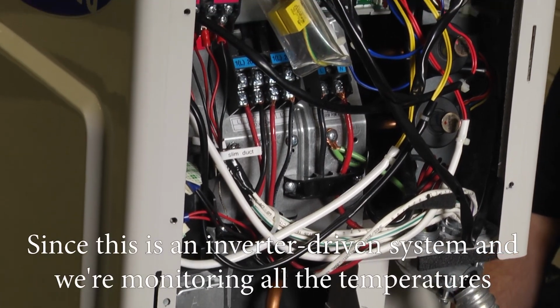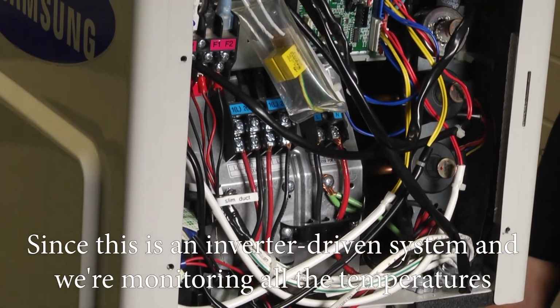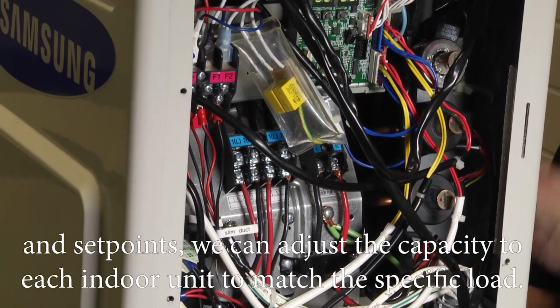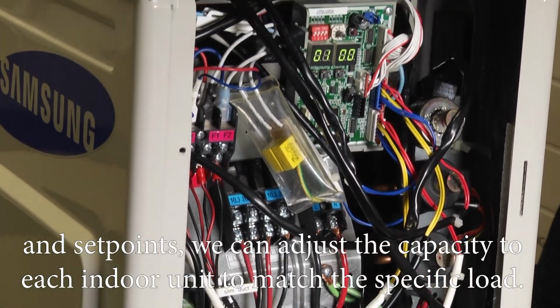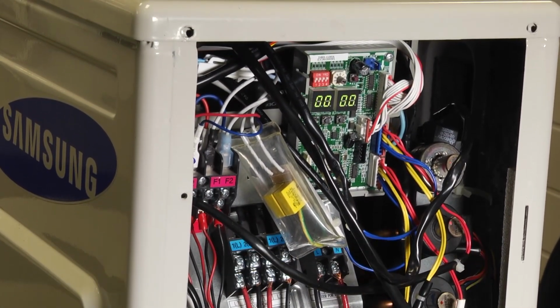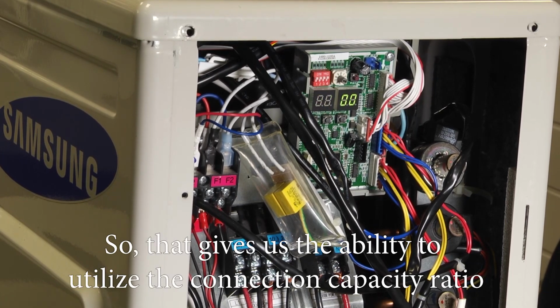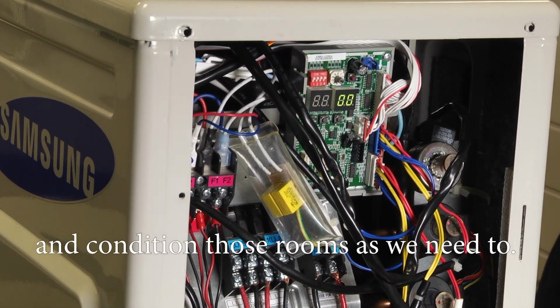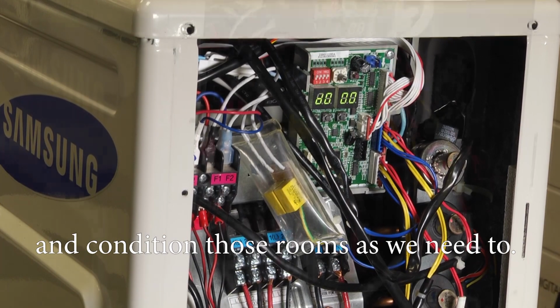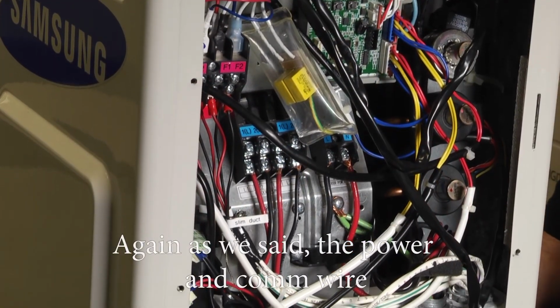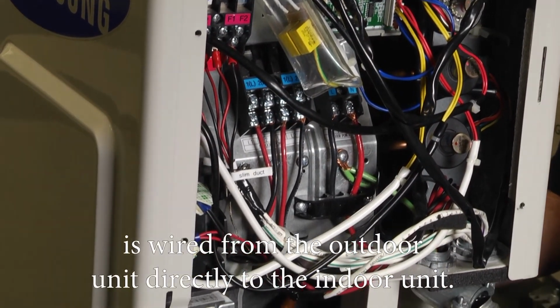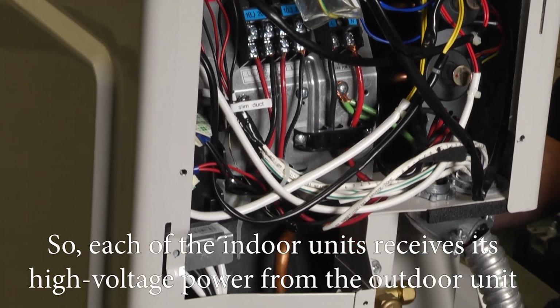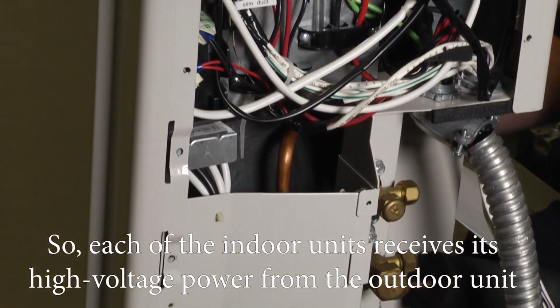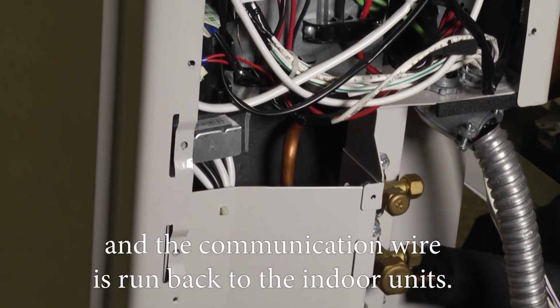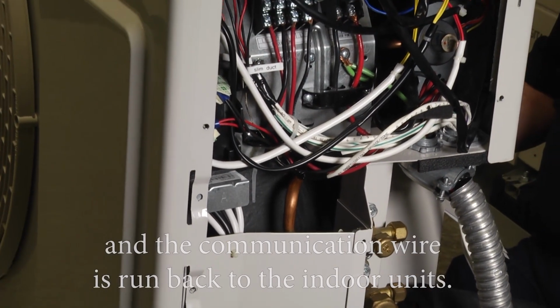Since this is an inverter-driven system and we're monitoring all the temperatures and set points, we can adjust the capacity to each indoor unit to match the specific load. So that gives us the ability to utilize connection capacity ratio and condition those rooms as we need to. Again, as we said, the power and comm wire is wired from the outdoor unit directly to the indoor unit. So each of the indoor units receives its high voltage power from the outdoor unit, and the communication wire is run back to the indoor units.